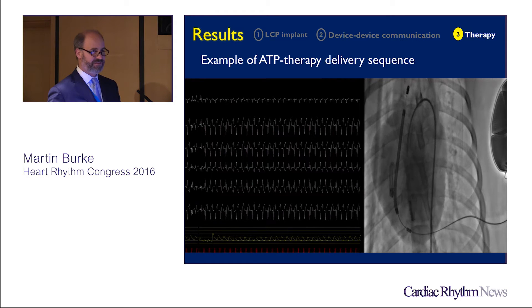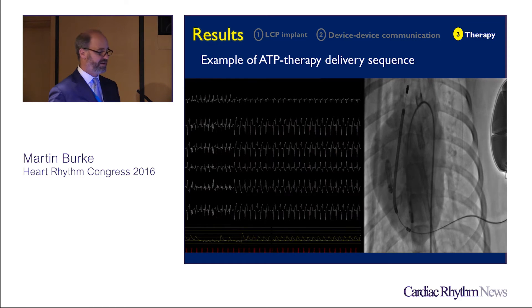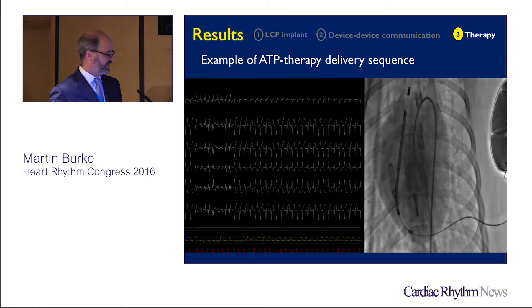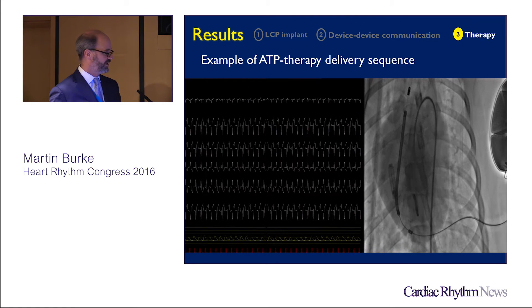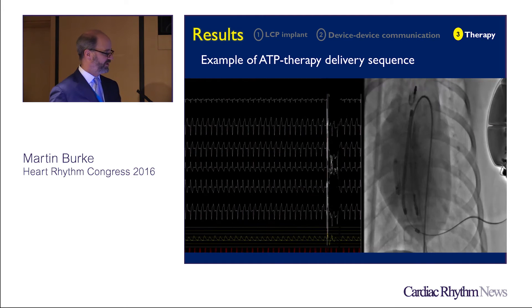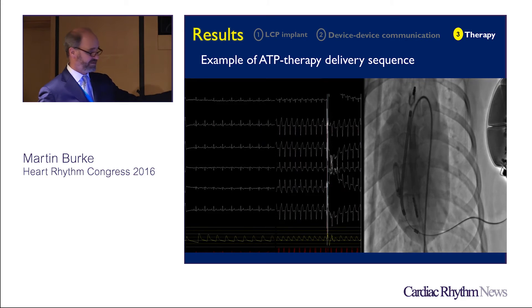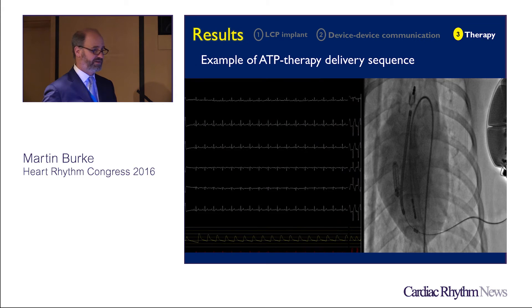There is no sensing dysfunction consequent to the communication — the device is still sensing and still delivering automatically in the series you'd expect when programming this ATP sequence. To be complete, we then delivered a countershock to confirm that post-shock communication occurred accurately and that both devices were impervious to the shock. This was a mimicked case of what we would naturally see clinically.